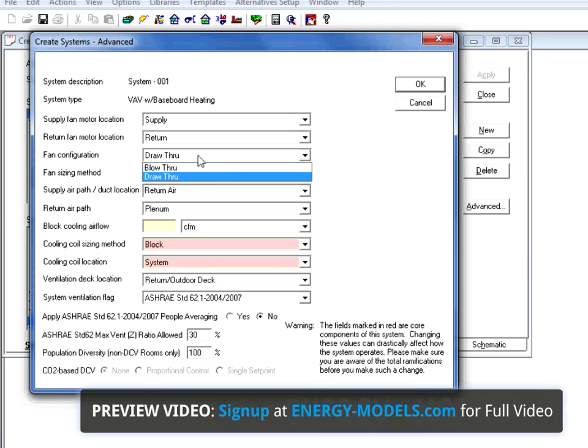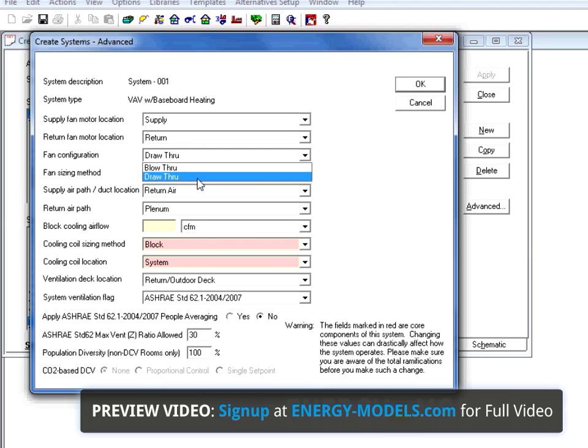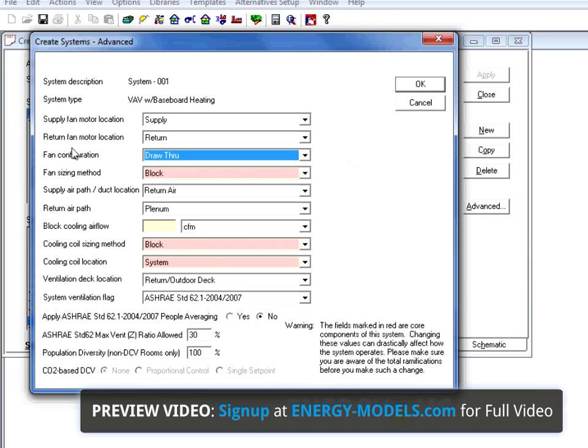The fan configuration can be set to blow through or draw through. While this isn't going to have a significant impact on your model, it's going to affect your psychrometry and should be taken seriously.